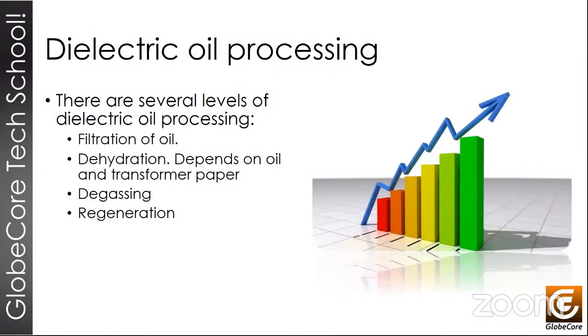Now, the processing of oil will change depending on what we want to perform. Dehydration is a type of processing that uses other means to remove water. Degassing is another thing that we're going to do to remove gas. And the regeneration or recovery of oil is, well, you can refer to it as microfiltration, in which we have a fineness of about 3 microns. Next slide, please.